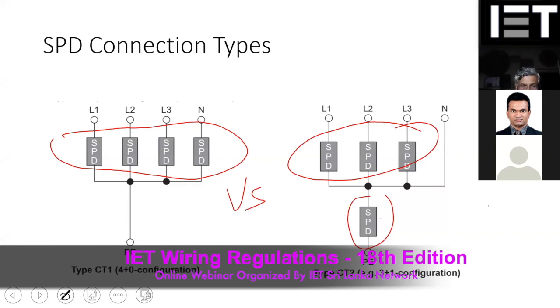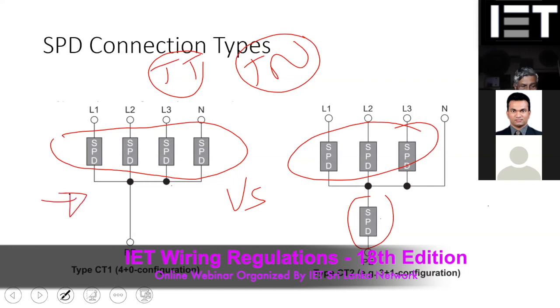The protection is the CT, because when you look at normally our installation, we have a TT arrangement versus a TN arrangement. Your connection pattern will depend on whether you have a TT arrangement or TN arrangement, and also what type of protection you want to have, whether you want a common mode protection or a differential mode protection. So if I use the first type in a TT arrangement, what is the problem? If I say the first type is not recommended for the TT arrangement, why is that? Can you imagine why the first arrangement is not recommended for the TT arrangement? Any idea?